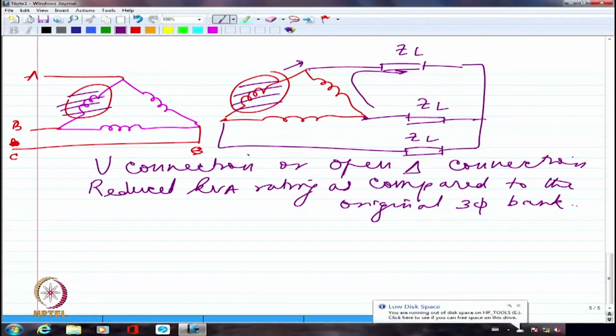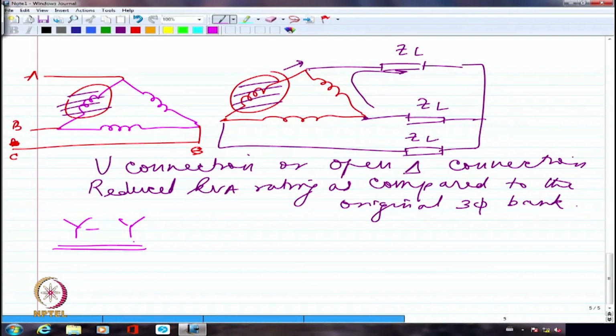The last one which we have still not discussed is the star-star case. As far as star-star is concerned, it is again no step up or step down, no phase shift, but this is one of the rarest configurations that are used anywhere, unless I ground the neutral. If the neutral is not grounded, it is not really a popular configuration. Let's see why star-star configuration without neutral grounding cannot be used very easily. What is the problem with this? Let us try to take a look.